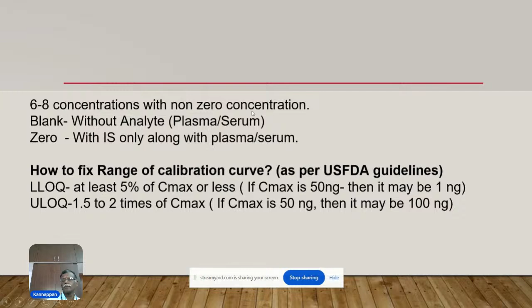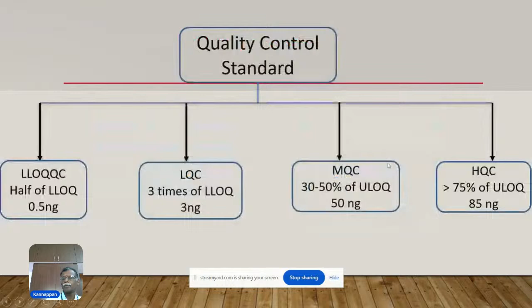And the medium quality control is 30 to 50% of the ULOQ. ULOQ is 100 nanogram, so 30 to 50% of the concentration will be 50 nanogram. And the high quality control is more than 75% of the ULOQ. Since ULOQ is 100 nanogram, we can fix it as 85 nanogram. So these three concentrations will also be included in the linearity range. The previous 8 concentrations, standards 1 to 8, plus these 3, so 11 concentrations. So the calibration curve and quality control standards will be included.